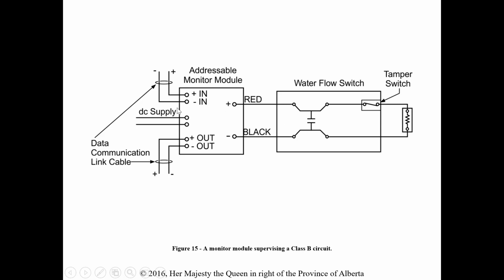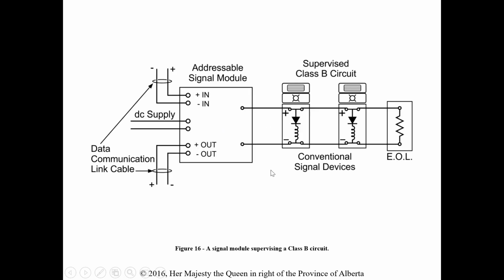And if there's a change of state, this module needs to know so that it can send that signal back to the panel. So we're still monitoring. If this tamper switch opens, this module is going to notice that and say, hey, my current has changed because I'm not going through the end-of-line resistor. And then it's going to send a signal back to the control panel saying, hey, we have a trouble scenario or a supervisory issue.